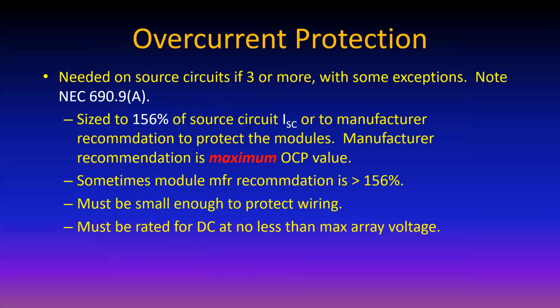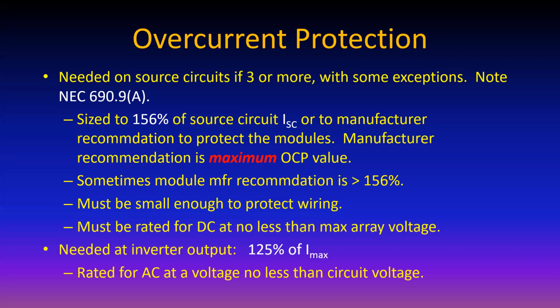Okay, overcurrent protection. Again, I'm not going to spend a lot of time on this because it's all in 690.9(A). You just follow the rules. And the important thing here is 690.9(A) has changed a couple of times between 2014 and 2020. So that's why you don't just follow the rules that you see in front of you. You take a look and see what 690.9(A) says right now for what's going on in your particular jurisdiction and follow that rule. Okay? At the inverter output, I don't think we're going to see this change. 125% of the maximum inverter current for the wire sizing. And that's also a good idea for the sizing of the overcurrent protection.